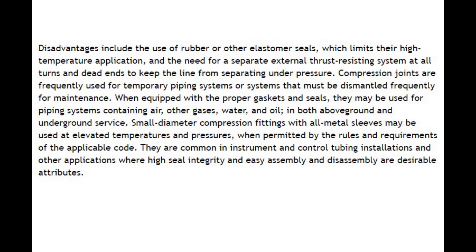Small diameter compression fittings with all metal sleeves may be used at elevated temperatures and pressures when permitted by the rules and requirements of the applicable code. They are common in instrument and control tubing installations and other applications where high seal integrity and easy assembly and disassembly are desirable attributes.